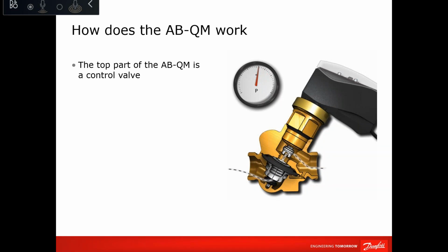Okay, and we have this question: PICVs of a smaller size have 2 test ports, while larger sizes have 3 test ports. Can you tell us why? What is the reason? The main reason is the size of the valve itself. You cannot fit 3 test ports on the small size. A big one, you can. There is a space for that. But the difference between the 2 and 3: on the 3 test port, you have P1, P3, before and after the whole valve, and P1, P2, before and after the differential pressure controller, and P2, P3. So here you can measure 3 DPs.